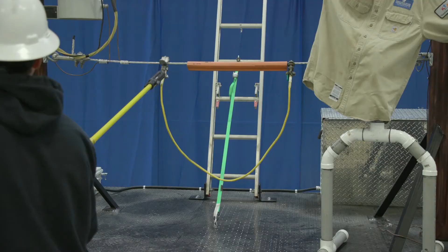So the last thing that we do after we indicate a line is dead or de-energized, we take a ground chain and put it on the wire, and it makes a short circuit to ground. If it was on, it's going to trip a device off somewhere. That's how we know a line is safe for us to work on.